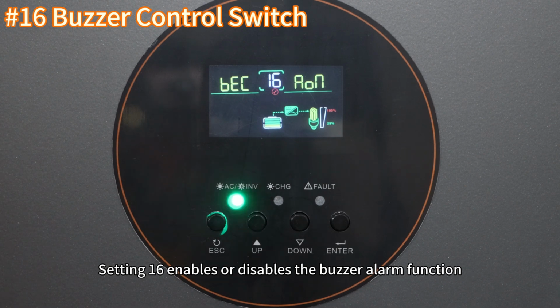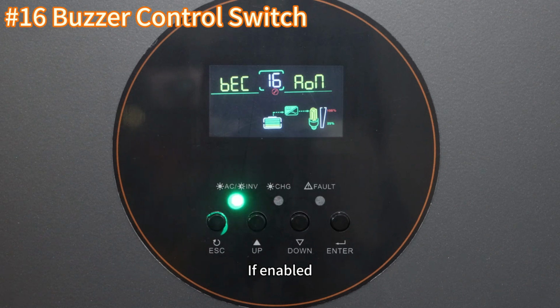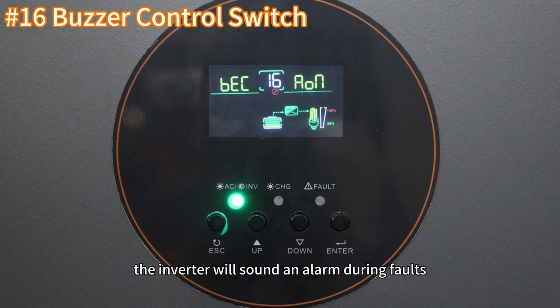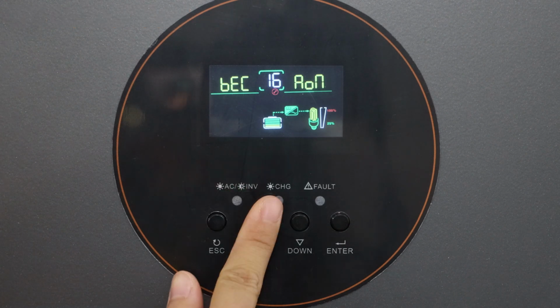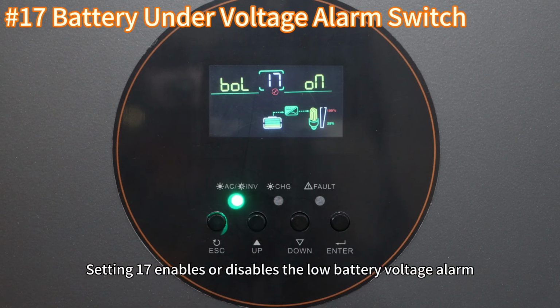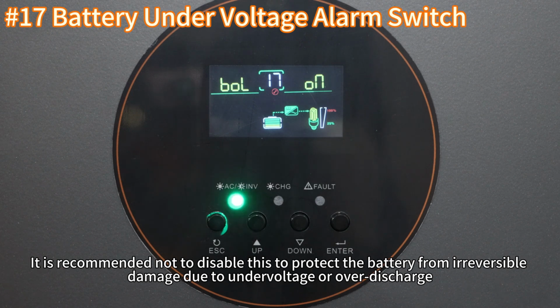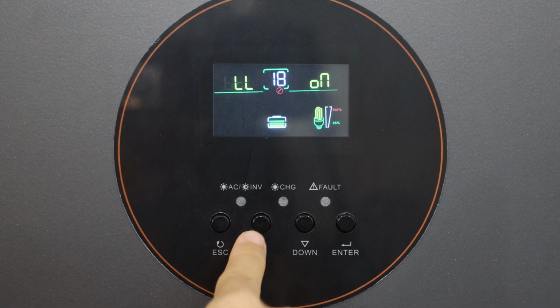Setting 16 enables or disables the buzzer alarm function. If enabled, the inverter will sound an alarm during a fault. Setting 17 enables or disables the low battery voltage alarm. It's recommended not to disable this, to protect the battery from irreversible damage due to undervoltage or overdischarge.